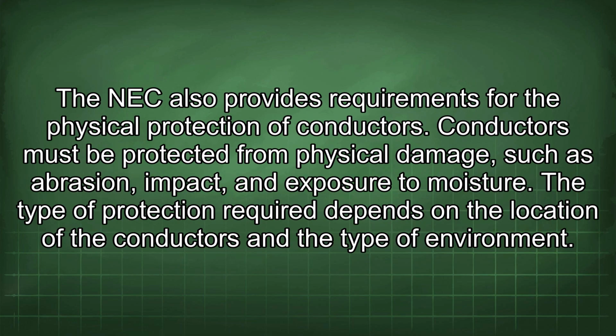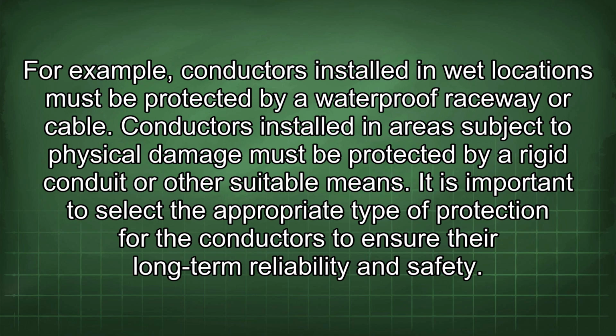The NEC also provides requirements for the physical protection of conductors. Conductors must be protected from physical damage such as abrasion, impact, and exposure to moisture. The type of protection required depends on the location of the conductors and the type of environment. For example, conductors installed in wet locations must be protected by a waterproof raceway or cable. Conductors installed in areas subject to physical damage must be protected by a rigid conduit or other suitable means. It is important to select the appropriate type of protection for the conductors to ensure their long-term reliability and safety.